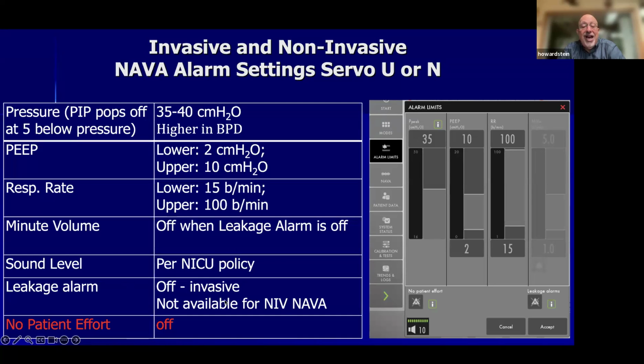With non-invasive NAVA, it's not available. With invasive NAVA, turn it off, or it'll alarm a lot. And most importantly, this no patient effort alarm must be turned off. This no patient effort alarm goes off every time the baby goes into backup ventilation.